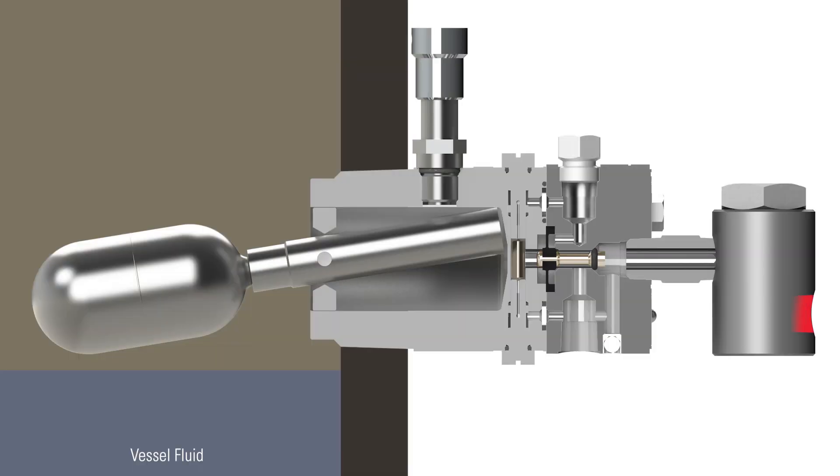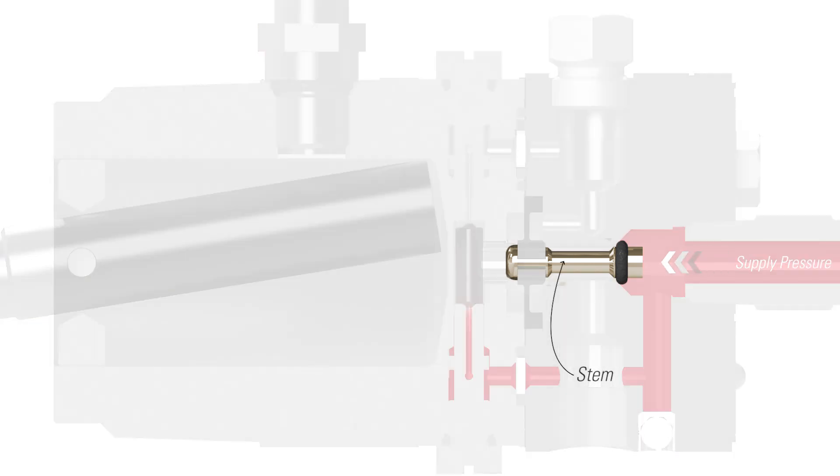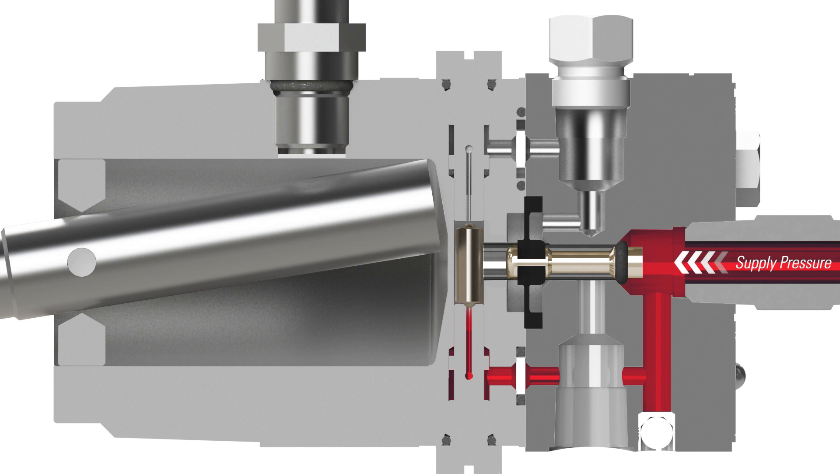Supply pressure comes in through the filter into the pilot body creating a force on the stem keeping it closed. The float lever is magnetically opposed to the magnet in the shuttle which has a check ball on the top and bottom to seal off the flow in either direction.